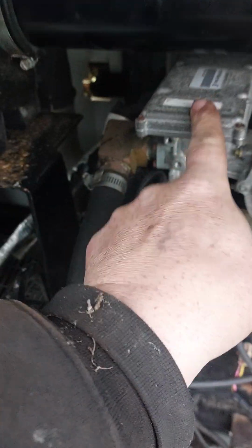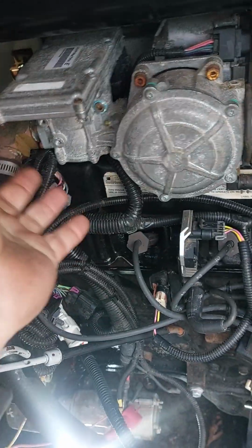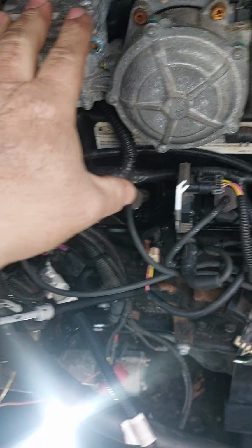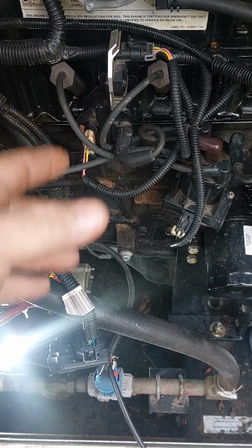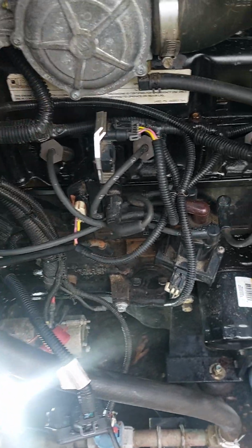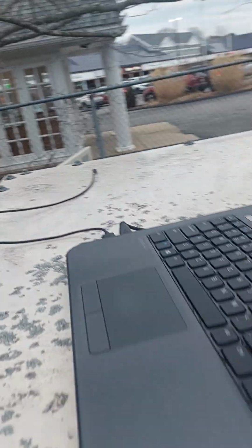It's lower than expected. This right here is the EPR, and it's integrated with an ECM. So anyways, this basically takes pressure from the fuel valve, regulates it down, and when it doesn't need much, it will chop it down. Right now, my base fuel pressure is about 5 inches of water column. So what I've done was, let me reset this fault.